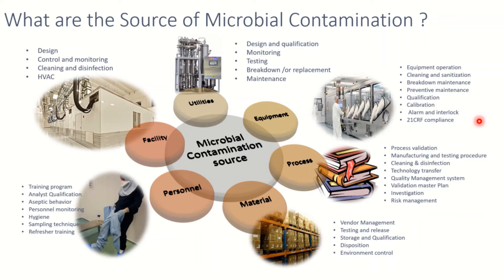Next is regulatory compliance — not just 21 CFR, but also EU Annex 1 and other CGMP documents which explicitly elaborate controls and requirements. For FDA, this includes 21 CFR Part 210, 211, and Part 11, which specifically addresses electronic signatures and electronic records. It is very important to have a digital track of who is operating machines, whether the person is trained, what interventions and changes were made during the process, and to review your audit trail. Unauthorized attempts on machines can have an extended impact on microbial contamination.